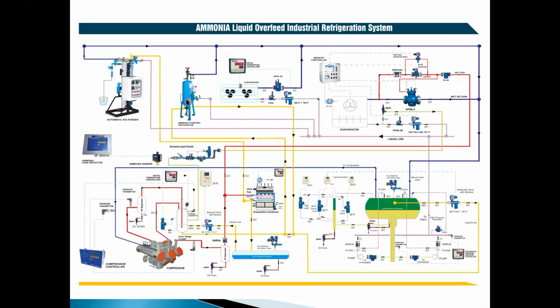Automation is being taken care of by the compressor control system. You have the ammonia detection system, the safety valves, level control for the pump vessel. We'll see more detailed controls for the pump vessel later on. Automatic purging systems, ammonia purification system, all can be implemented. This schematic shows you what can be implemented in a refrigeration plant.